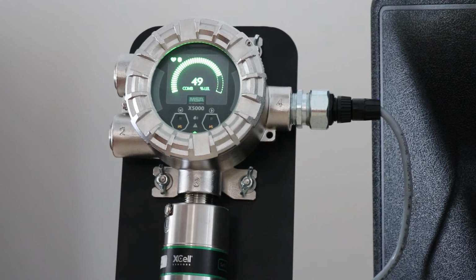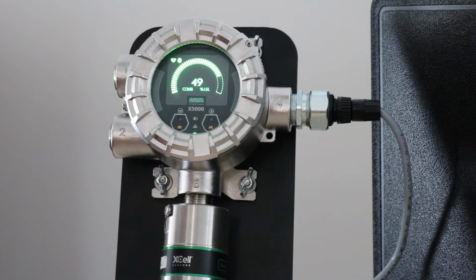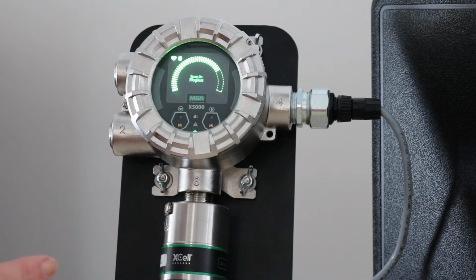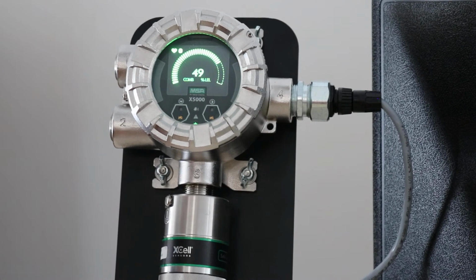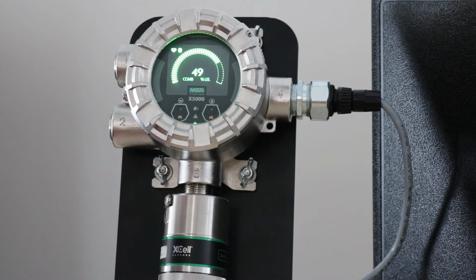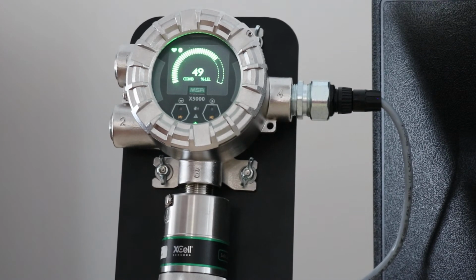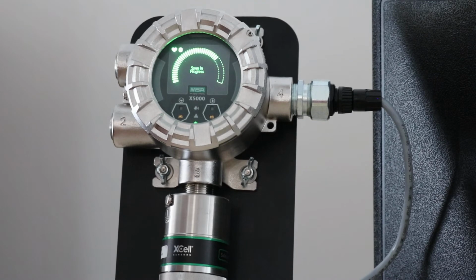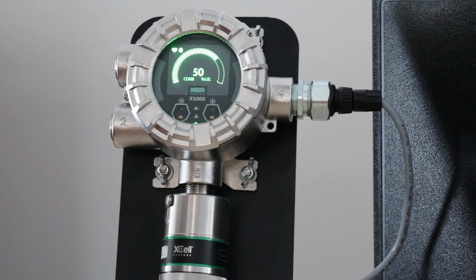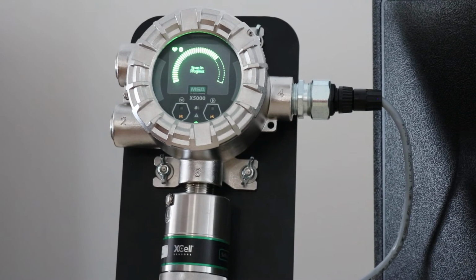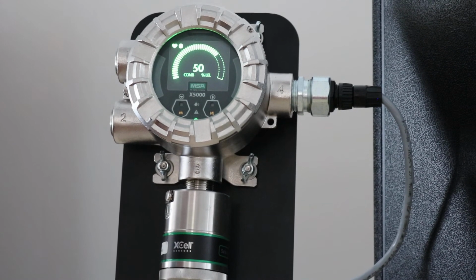One thing people do is, with an LEL sensor, it should be on a remote junction box, which is sold separately, and mounted high if it's methane, for instance, because it's lighter than air. And in a case like that, this procedure may take a little bit longer, not dramatically, but you have to fill the tubing to get up to your sensor. It also, of course, takes a little bit more of your span gas that way, but it makes it better than getting a ladder out and climbing up to your sensor.